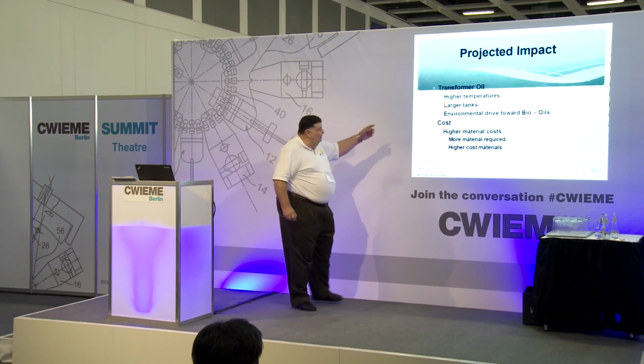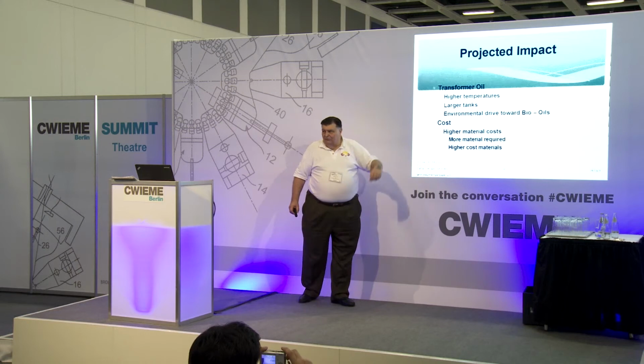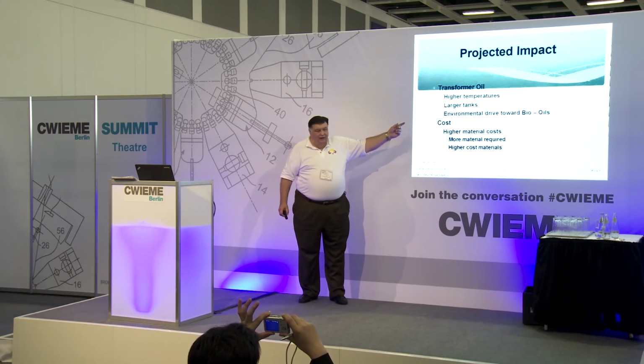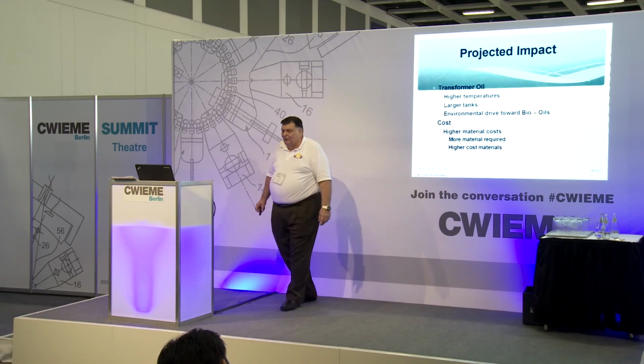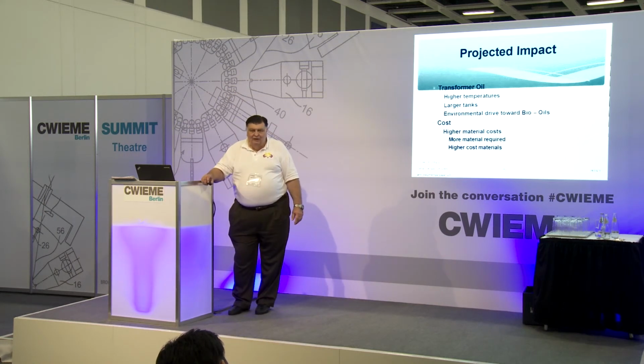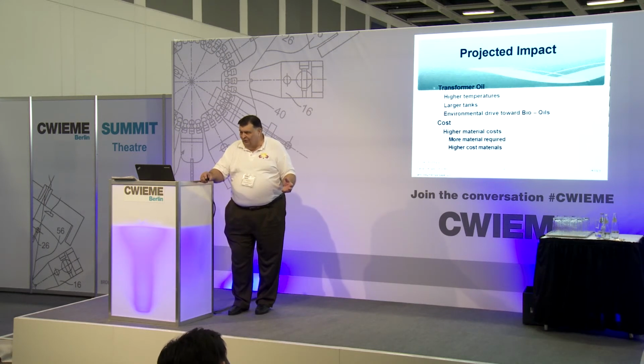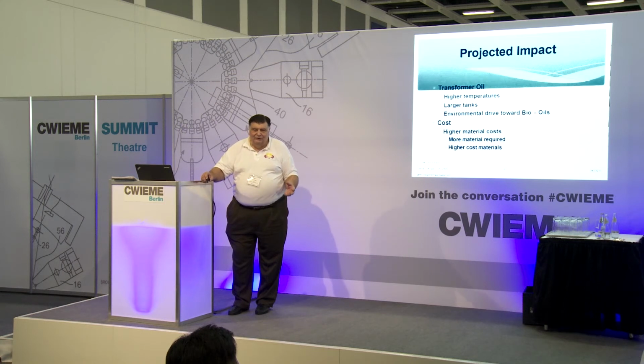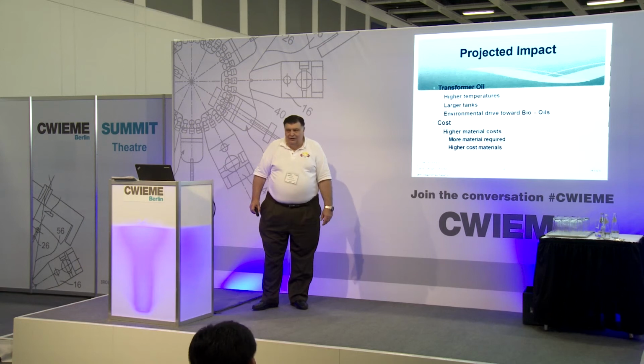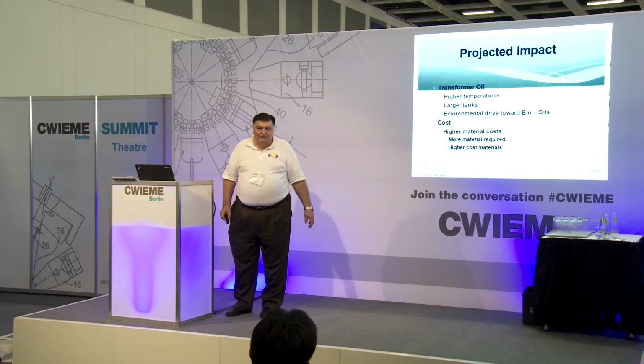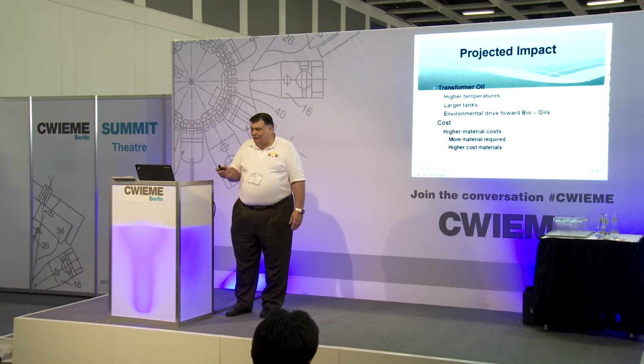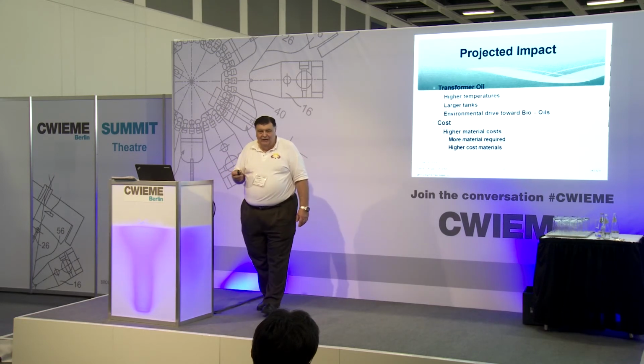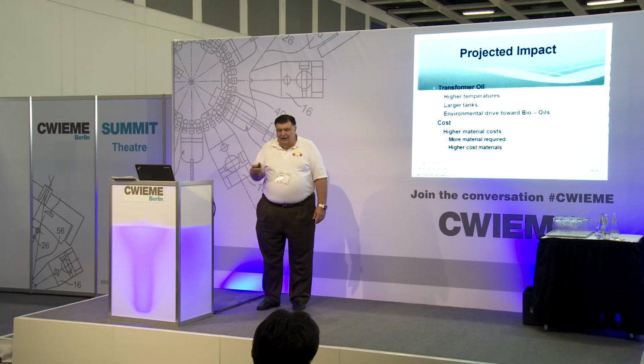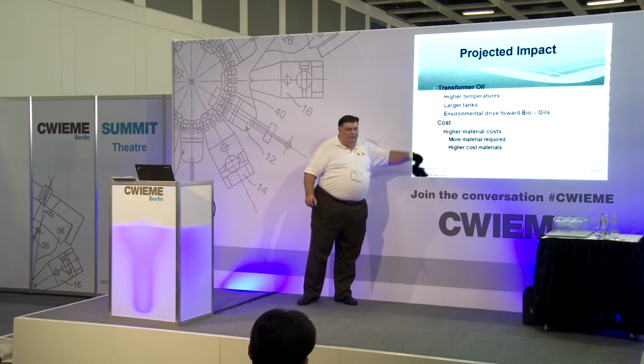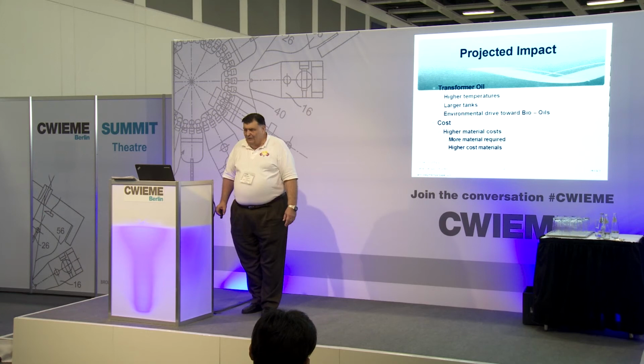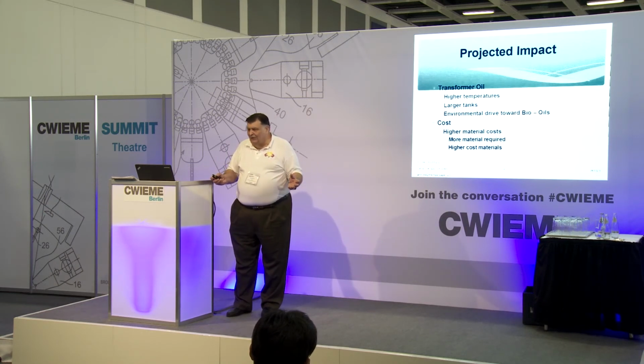Transformer oil. We have the possibility of the transformers running at higher temperatures, which is a benefit for the bio-oils. Larger tank size. There's a continued environmental drive toward the bio-oils. One of the fallbacks is that when we talk about hazmat spills, hazardous material spills, most regulations around the world today consider a bio-oil the same as a petroleum-based oil as far as being a hazardous material in a spill. If that changes around the world, and the various countries regulate that bio-oil does not have to be treated as a hazardous material, then you're going to see a tremendous drive toward the bio-oils. But right now, they and the petroleum-based oil are treated exactly the same in the case of a spill.